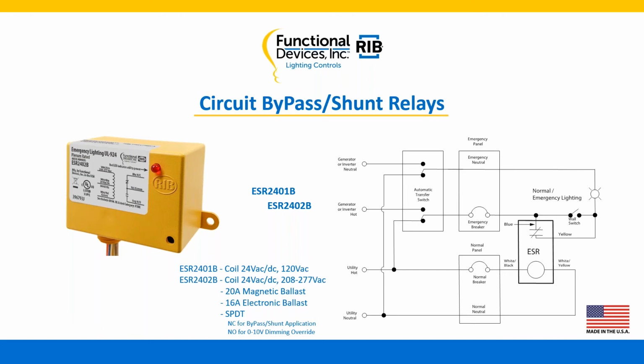Again, this is more of a circuit bypass shunt relay. It is a very hefty relay, 20 amp magnetic ballast. We do have a nice feature here with a 16 amp electronic ballast. It is a single pole double throw relay. In this application over here to the right, we're using the normally closed side, and you're using the normally closed contacts to create that path for that emergency light to come on. If you look at the drawing and the actual photo over here to the left, you'll see the normally open side towards the bottom. This can also be used as a 0 through 10 volt dimming override relay. We do offer that. It sometimes is used, sometimes it's not. Primarily, this is a shunt relay just to go around those wall switches and so forth.